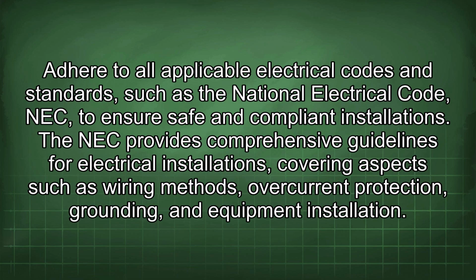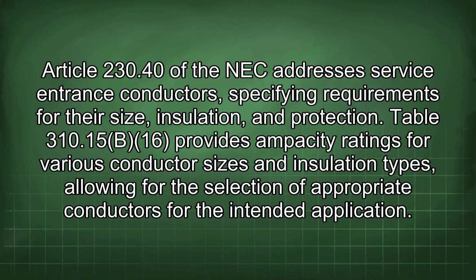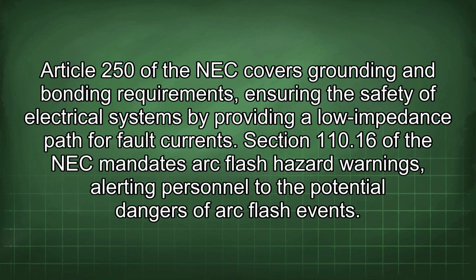Adhere to all applicable electrical codes and standards, such as the National Electrical Code, NEC, to ensure safe and compliant installations. The NEC provides comprehensive guidelines for electrical installations covering aspects such as wiring methods, overcurrent protection, grounding, and equipment installation. Article 230.40 of the NEC addresses service entrance conductors, specifying requirements for their size, insulation, and protection. Table 310.15(B)(16) provides ampacity ratings for various conductor sizes and insulation types, allowing for the selection of appropriate conductors for the intended application. Article 250 of the NEC covers grounding and bonding requirements, ensuring the safety of electrical systems by providing a low impedance path for fault currents.